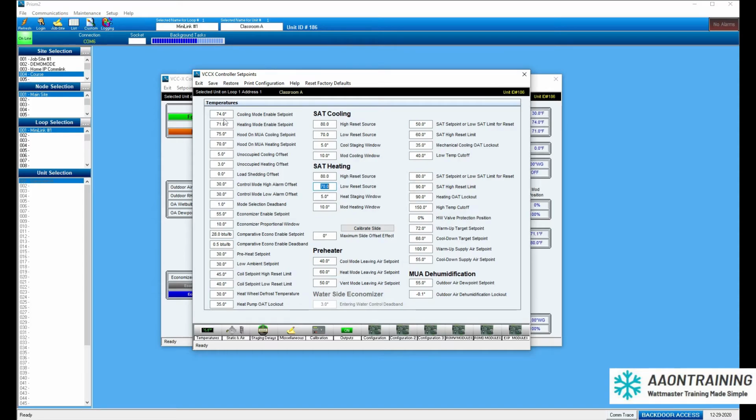And that's why every single technician who does a really good job, or AAON rep, who does a really good job with tweaking and tuning a system, who takes pride in it, will start using decimal places. They will start really figuring out what the temperature is in the space, what's common for this space, how much fresh air you're putting into the system, and then they'll make sure to put all these set points in accurately, and not just put in kind of a default option here.